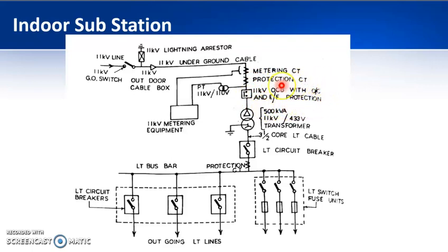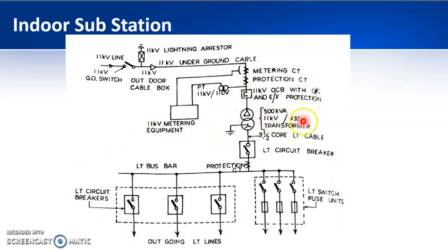From the protection CT, the supply is given to an 11 kV oil circuit breaker, and from the circuit breaker it is given to the transformer. From this point onwards, everything is housed inside the substation. You will have an 11 kV by 433 volt transformer with secondary delta-star connected, and therefore you are using a three-and-a-half core LT cable. From there it goes to the LT circuit breaker.